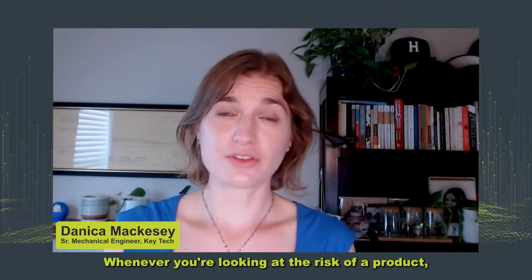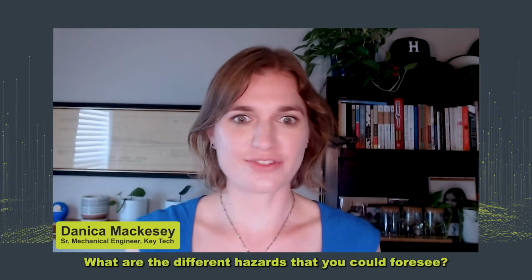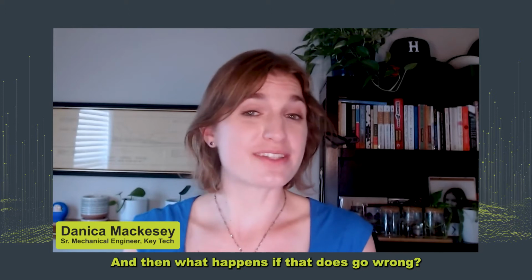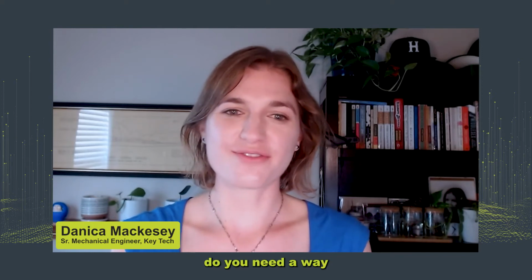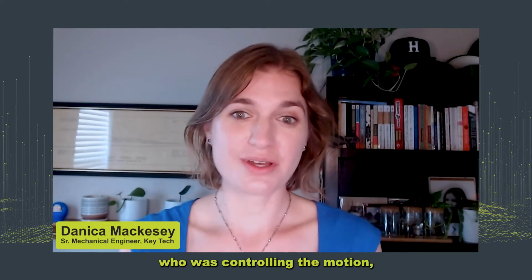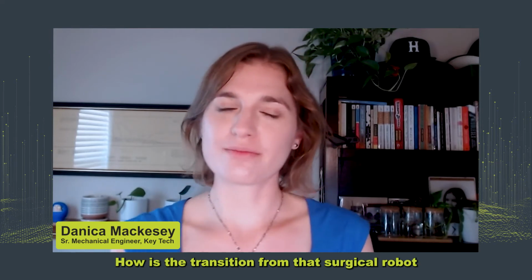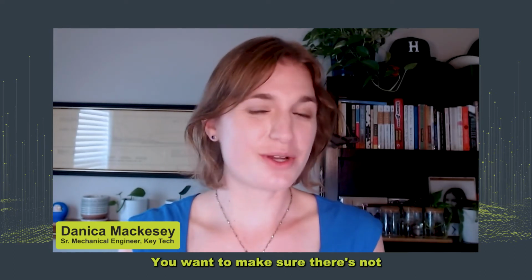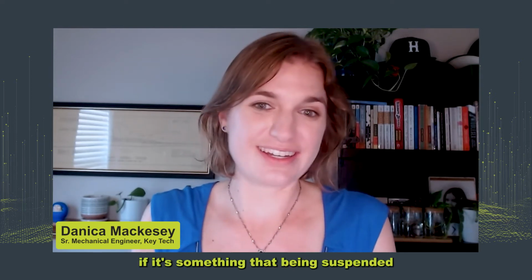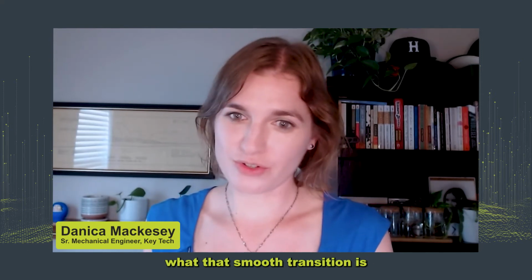Sure. Whenever you're looking at the risk of a product, you want to think about what are all of the ways that something could go wrong? What are the different hazards that you could foresee? And then what happens if that does go wrong? And so, with what you're talking about, what we had seen is, do you need a way for the surgeon to take back over where maybe your robot was the one controlling the motion, but now something happened? You want to have a manual override. How is the transition from that surgical robot controlling the motion to your operator going to happen? You can imagine if it's something that's being suspended in air inside of a patient, it can't just drop at some point. So you really need to consider what that smooth transition is.